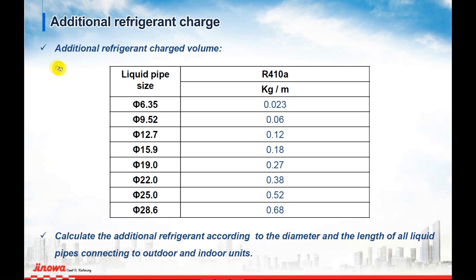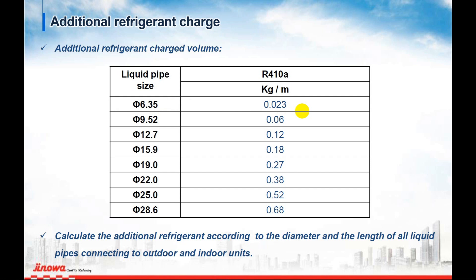For example, first we talk about the 6.35. You have to add 0.023 kilograms per meter. That means if your system has the pipe size 6.35, 10 meters, you have to add 0.023 kilograms per meter.